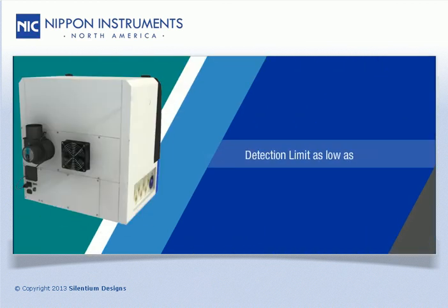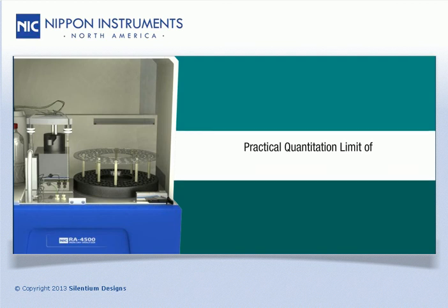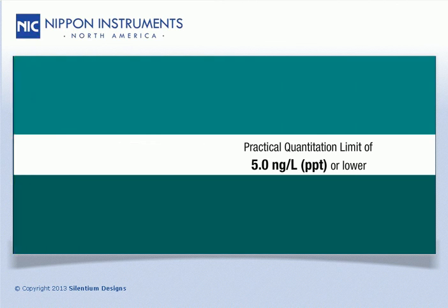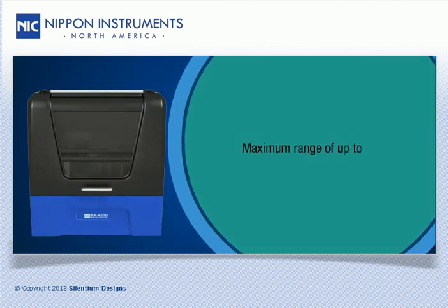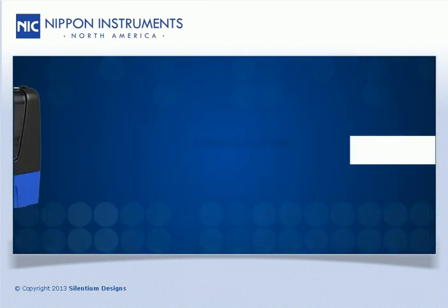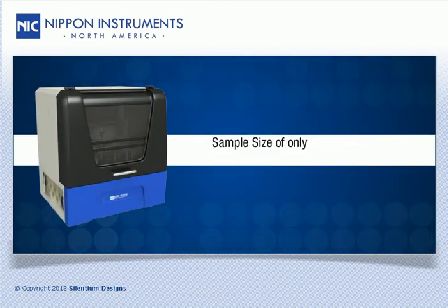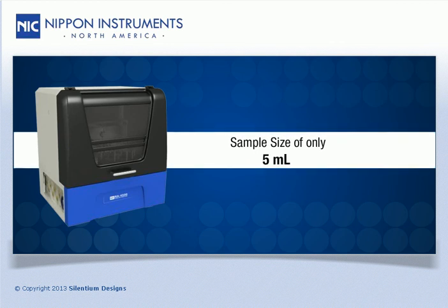The RA4500 offers a detection limit as low as 0.5 nanograms per liter or parts per trillion, a practical quantitation limit of 5 nanograms per liter or parts per trillion or lower, and a maximum range of 100 micrograms per liter or parts per billion. It is capable of achieving these near trace level mercury measurements with only 5 milliliters of sample.